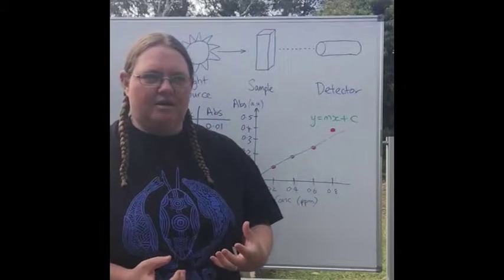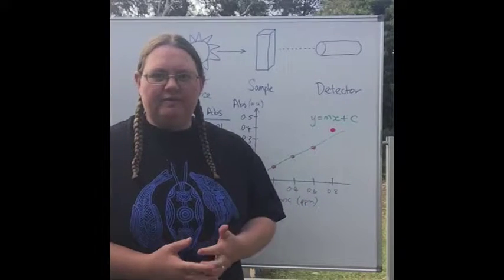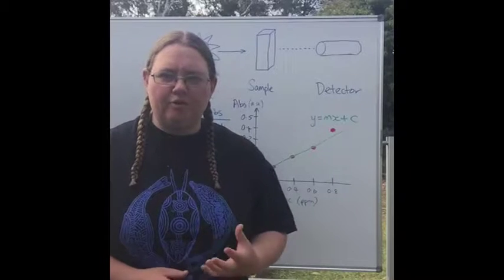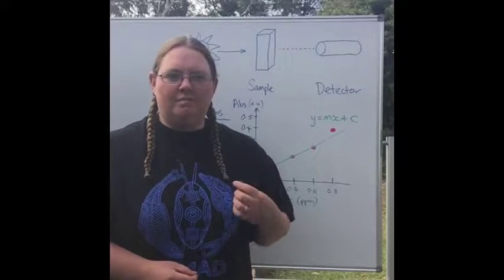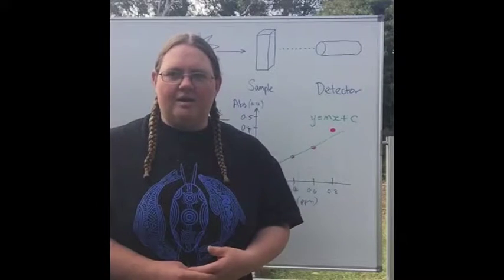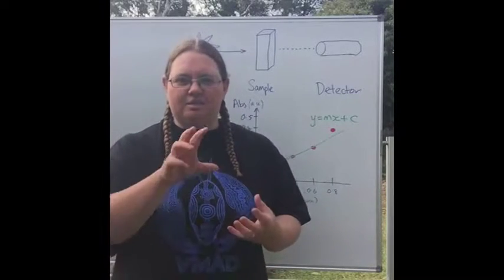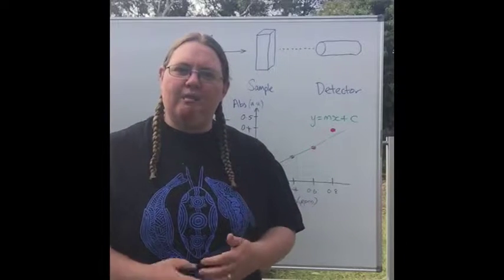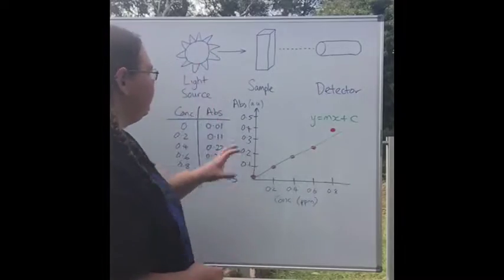In UV-visible analysis, you would use what's called a monochromator. If you think about the word mono, it means one, and chroma is color. A monochromator essentially pulls out one color or one wavelength for you to use in your UV-visible analysis.